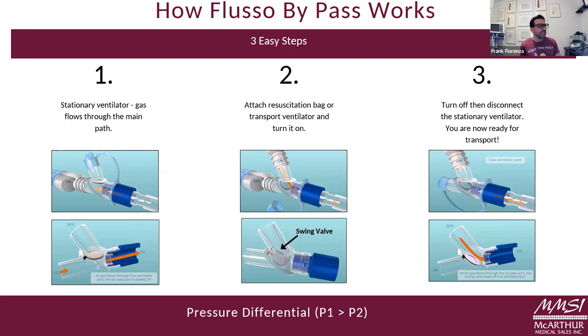So if we look at step one, gas going from the stationary ventilator straight through to the patient port. The valve is closed to the bypass port. Patient's being ventilated exactly as they would anywhere else - there's no difference to what's going on in every hospital today. In the image below, you can see how the valve is closed off.